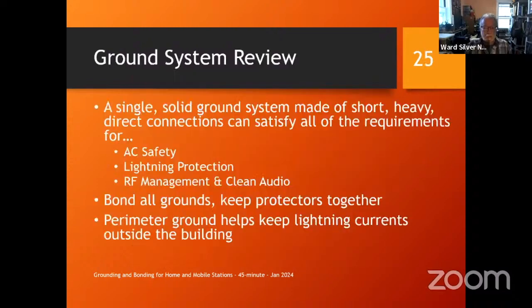Ground system review. A single ground system, short, heavy, direct connections, satisfies all of the requirements for these 3 things. You want to bond all of your grounds. You don't want your AC safety ground separate from your lightning ground, separate from your RF ground. Don't do it. They all have to be connected together. Keep your protectors together so they all fire at the same time and minimize voltage difference, and create your perimeter ground outside to keep your lightning current outside the building.